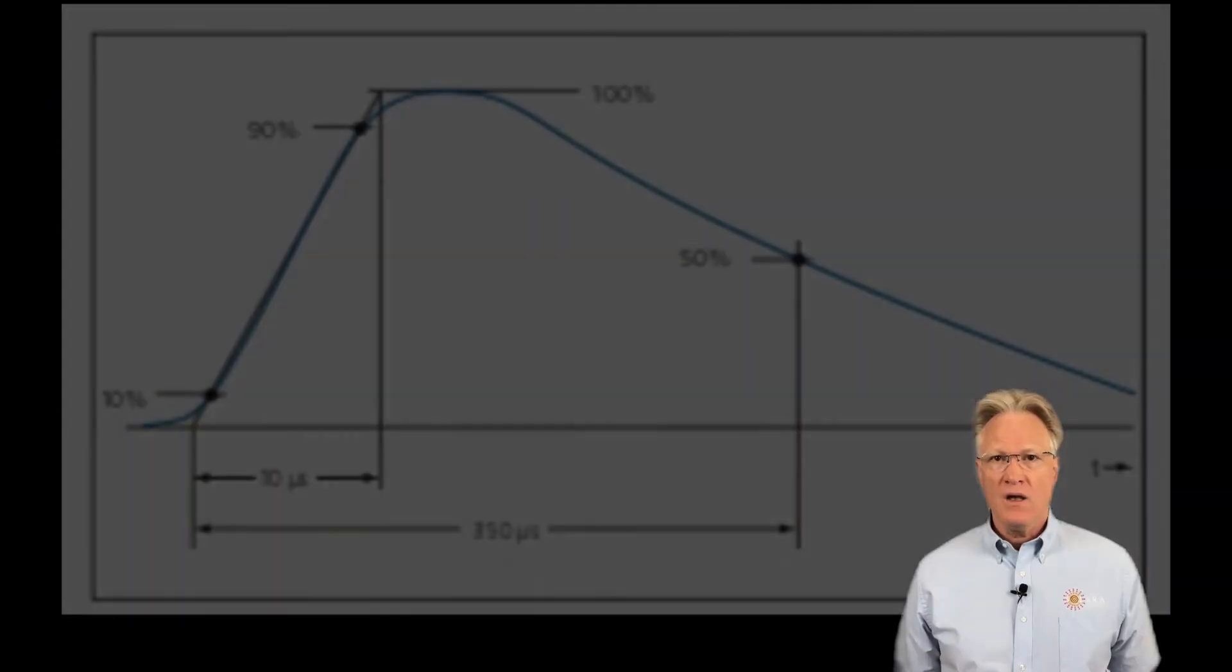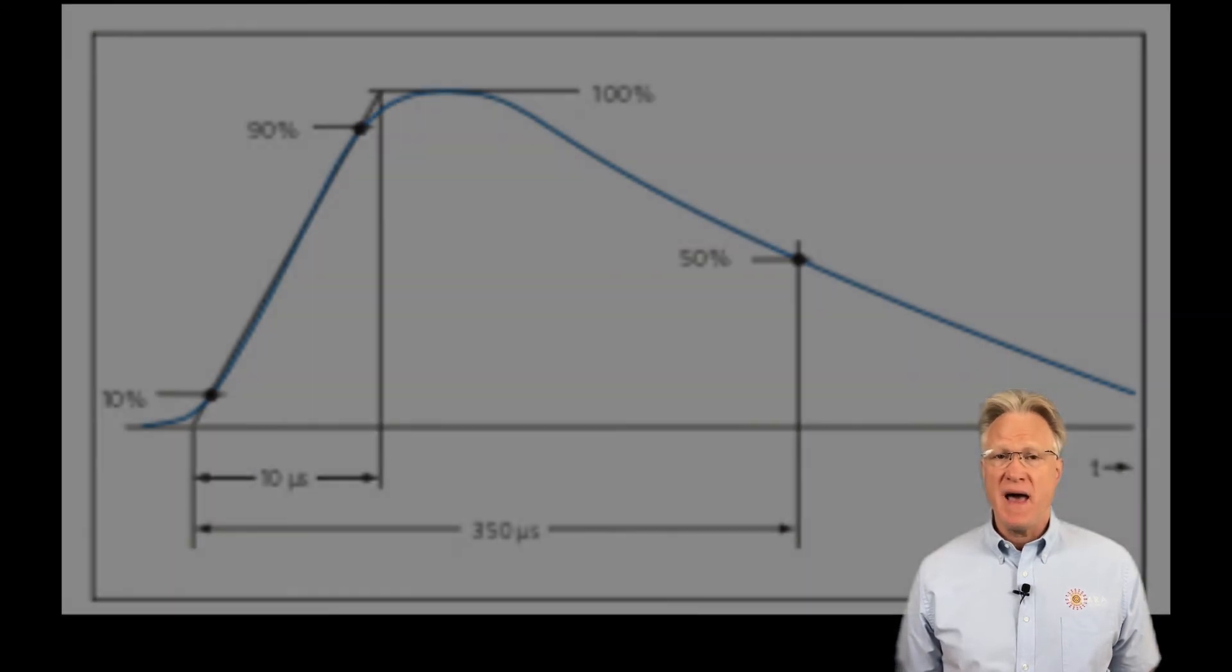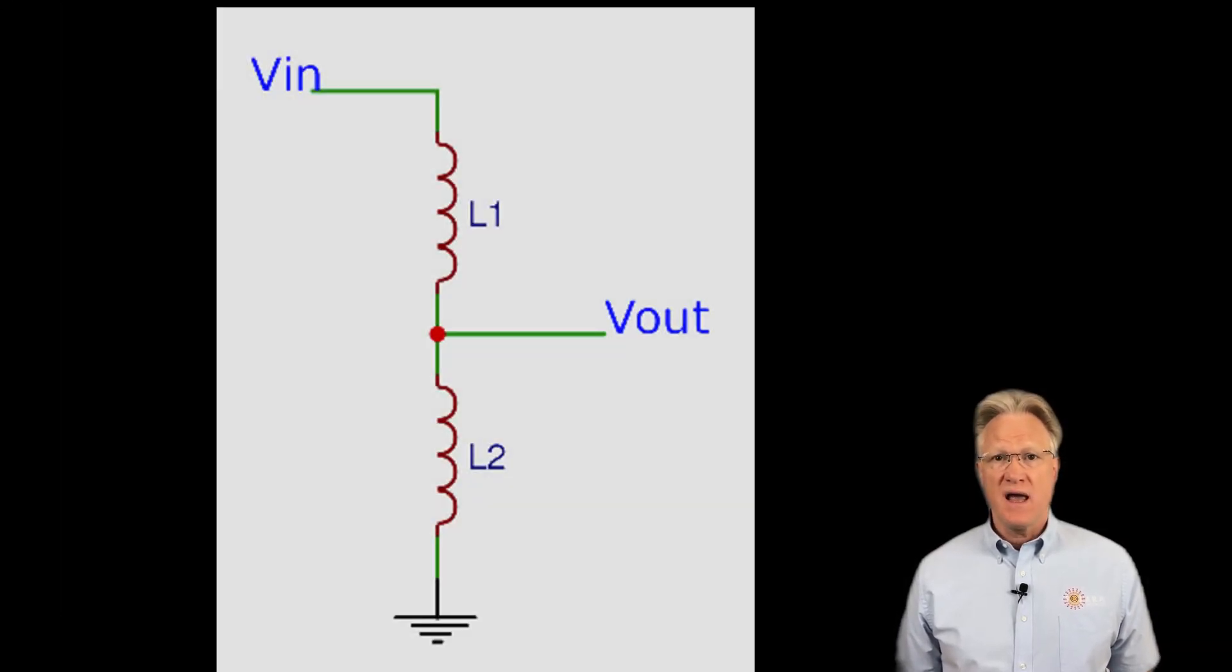Recall from my last video, absorbing the energy is problematic since it's so large. Also recall lightning is a pulse, so inductance matters. We're designing an inductive divider with high inductance above the top of the soil and low inductance below the soil.